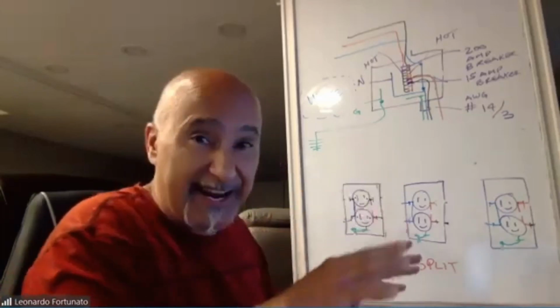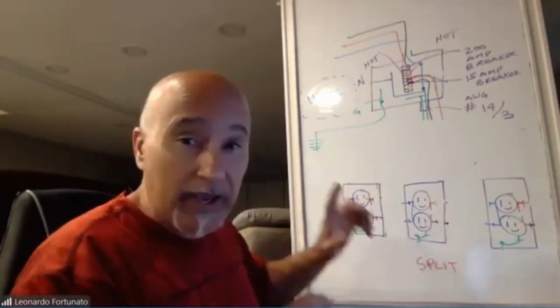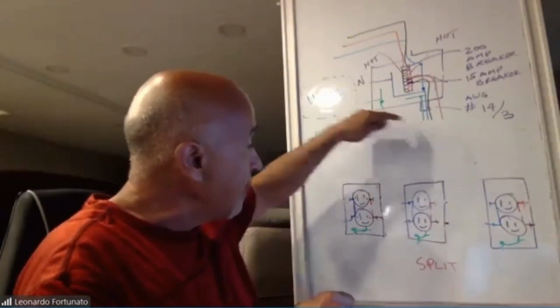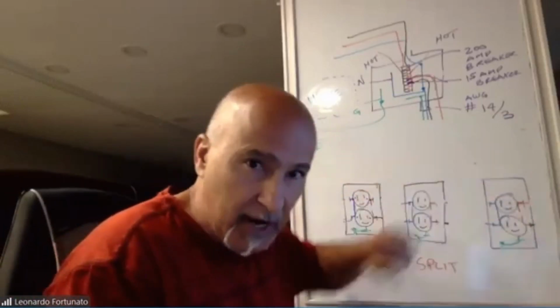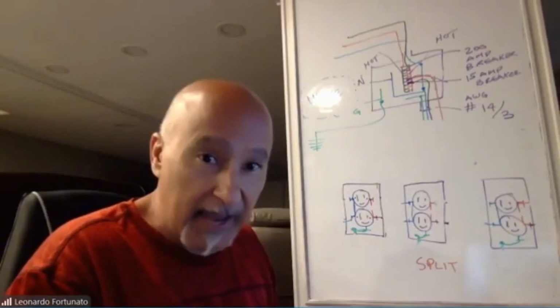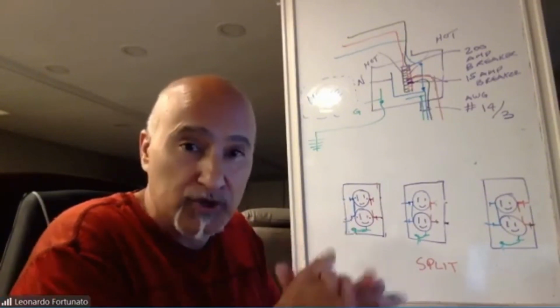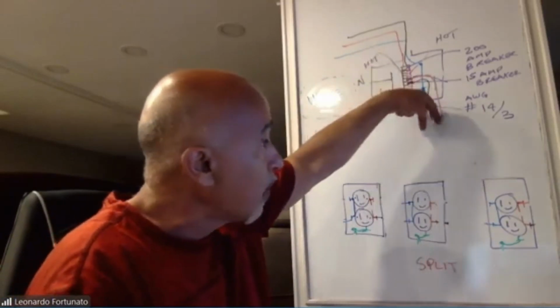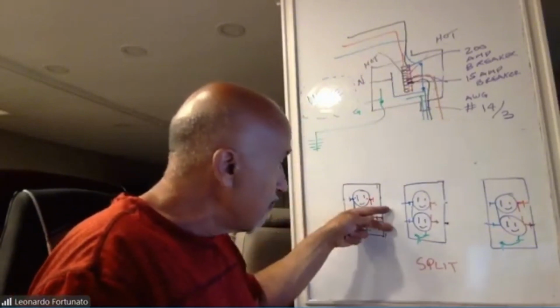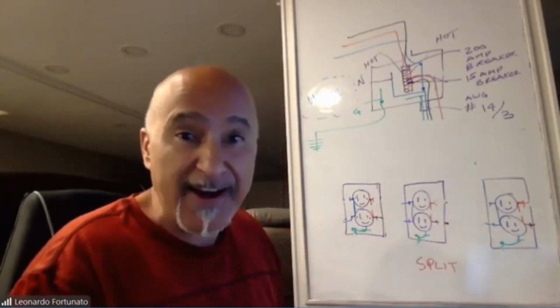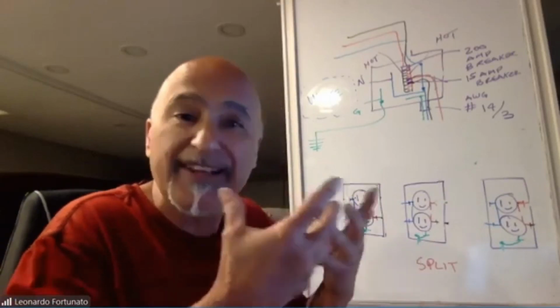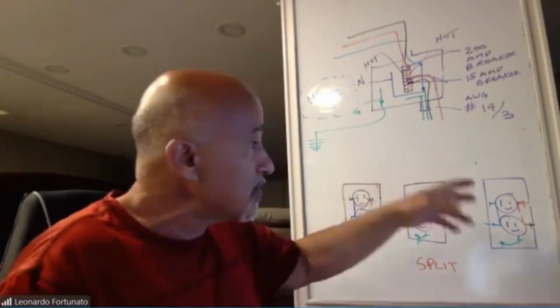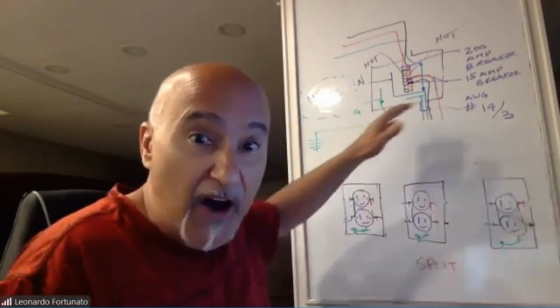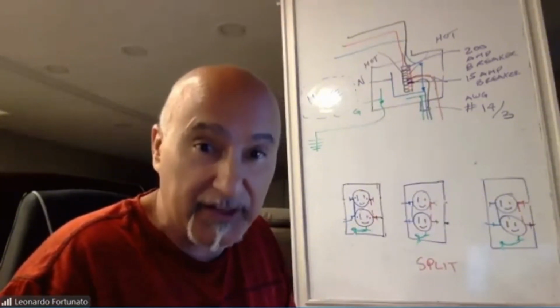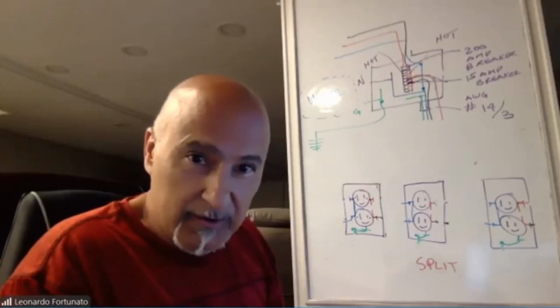Okay, 14-3 in this scenario, because I've got split receptacles, it's allowing me to run one cable from the panel to this receptacle, to this receptacle, to this receptacle. I am using less wire, and it's going to cost me less money and time to do. The other option is 2 circuits. I would have to run 2 14-2s, 2 14-2s, 2 14-2s. Now I have an extra neutral, and it's also starting to fill my boxes up too much. Imagine these receptacles being 50 feet away from the panel. Now I have to run 100 feet of 14-2 as opposed to 50 feet of 14-3. So we take this into account.